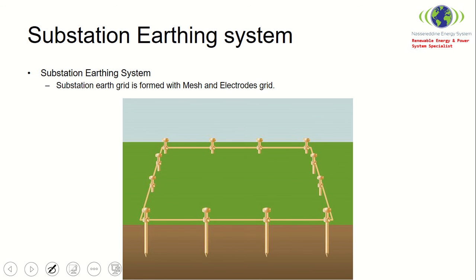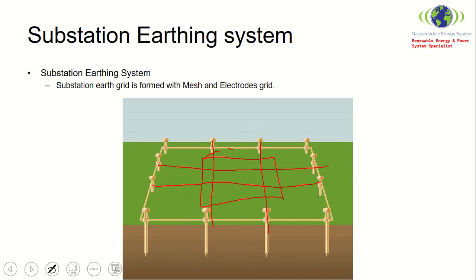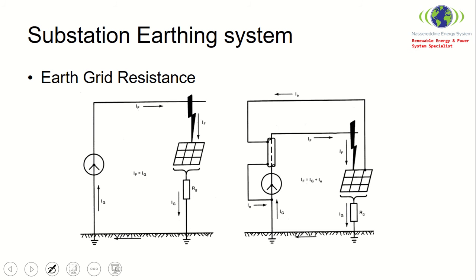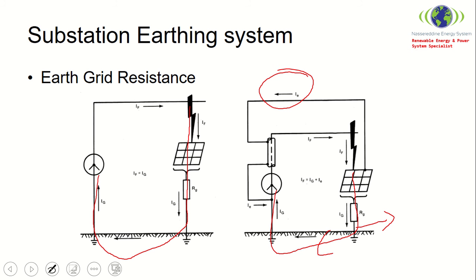A substation is usually formed of a mesh that takes into consideration the location of the building and bonding to it. Regarding earth grid resistance: if there is a fault on a transmission line, the current flows back to the star. If there is an auxiliary path, that path carries the fault current without it all going into the ground. This auxiliary path could be an overhead earth wire, a cable screen, or an earth continuity cable.